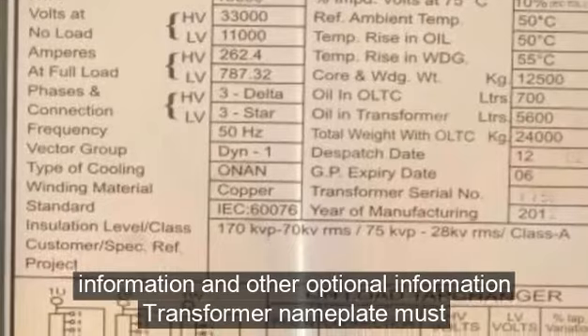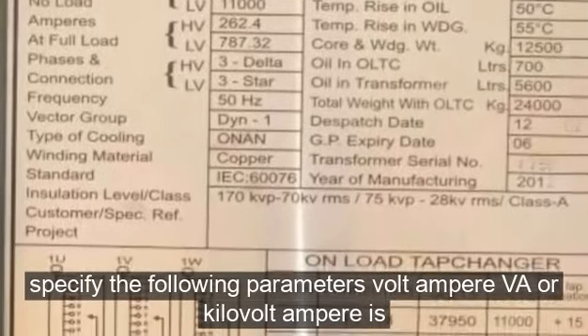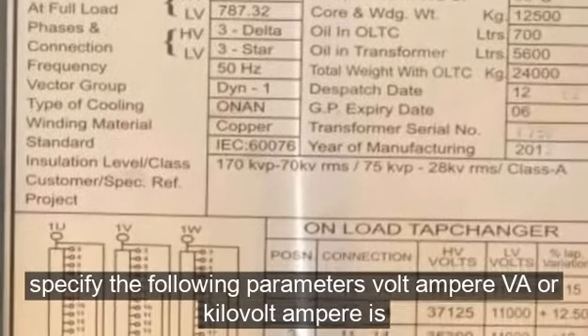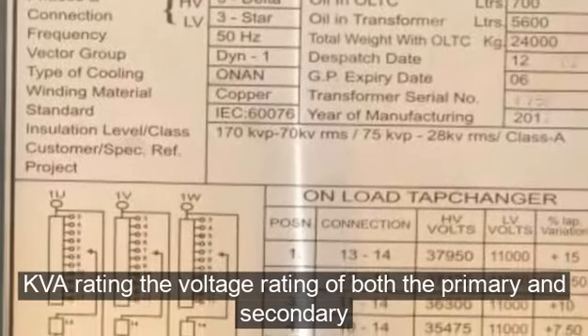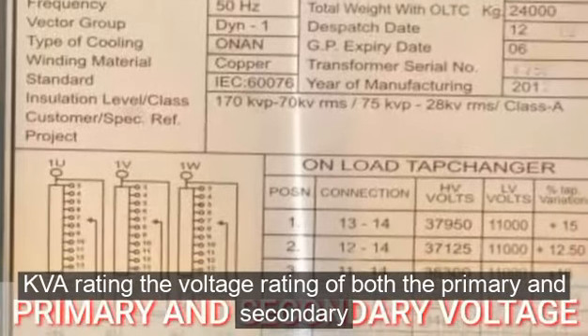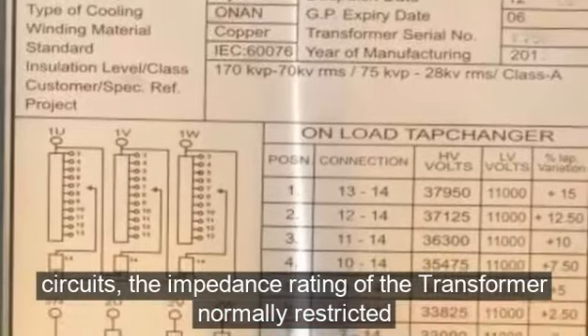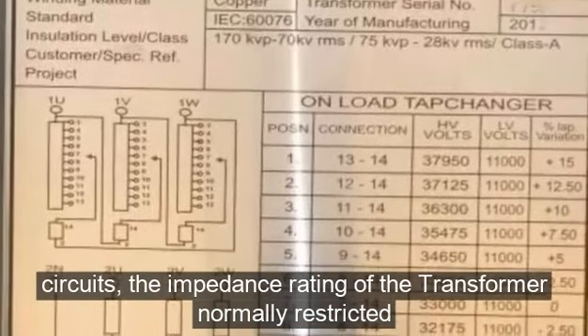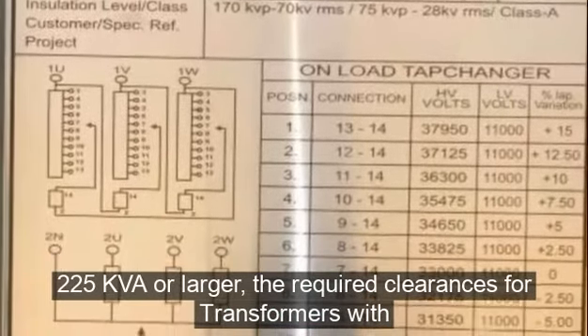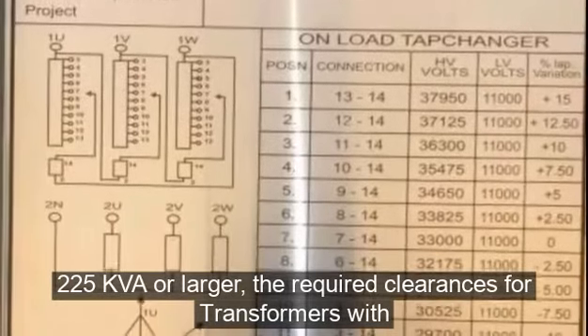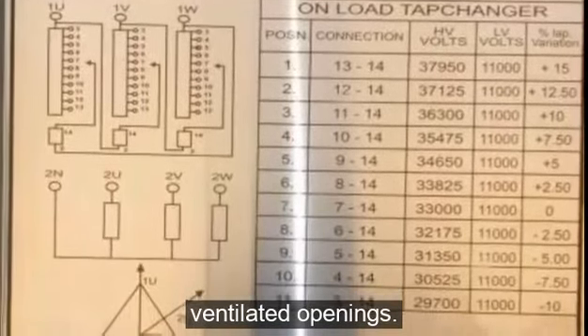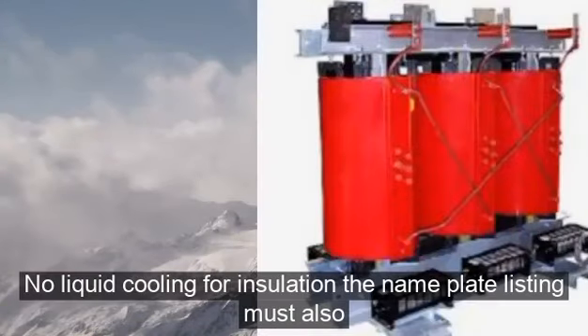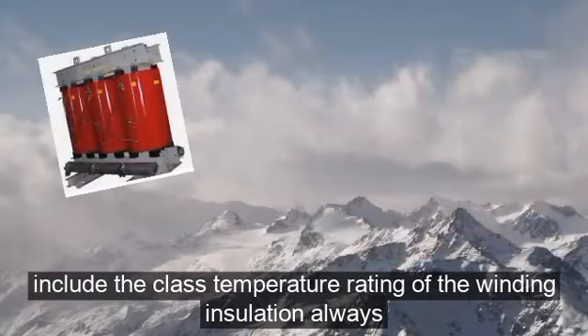The transformer nameplate must specify the following parameters: volt-ampere (VA) or kilovolt-ampere (kVA) rating, the voltage rating of both the primary and secondary circuits, the impedance rating of the transformer, normally restricted to 25 kVA or larger, the required clearances for transformers with ventilated openings, the amount and kind of insulating liquid where used. On dry-type transformers, no liquid coolant or insulation. The nameplate listing must also include the class temperature rating of the winding insulation.